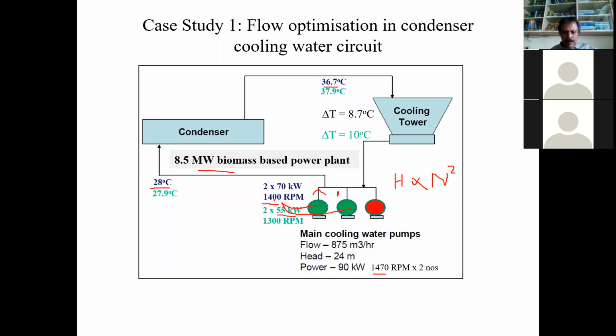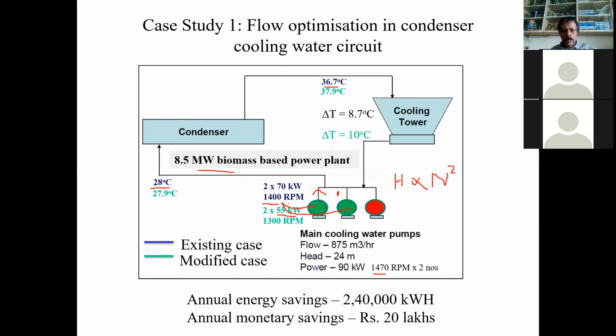So by reducing 100 RPM for these pumps and increasing the range of the cooling tower, we are able to save this much power. The annual savings by operating at this point is 2,40,000 kilowatt hours, and the monetary savings is about 20 lakhs.